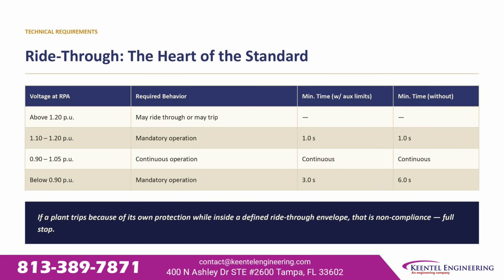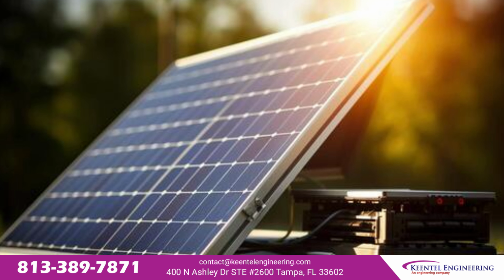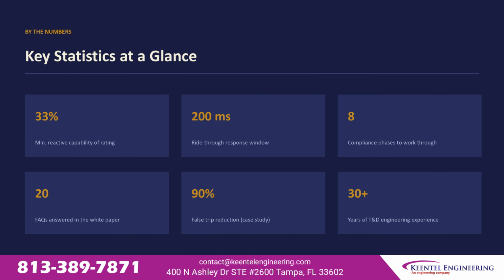Above 1.20 per unit voltage, a plant may ride through or may trip. Between 1.10 and 1.20, mandatory operation for at least 1 second. Between 0.90 and 1.05, continuous operation. No exceptions. Below 0.90, mandatory operation for 3 to 6 seconds, depending on auxiliary limits. And here's the line that matters most. If a plant trips because of its own protection while it's inside a defined ride-through envelope, that's non-compliance. Full stop. Let's recap the numbers that define this standard.